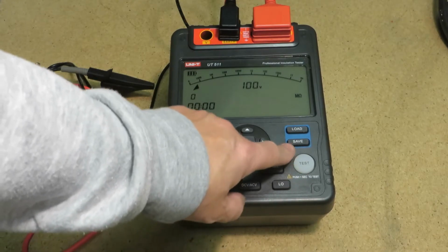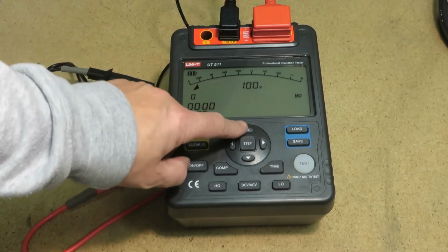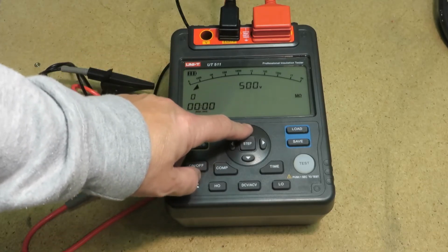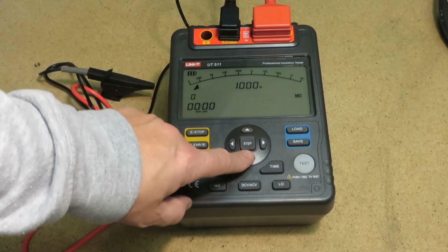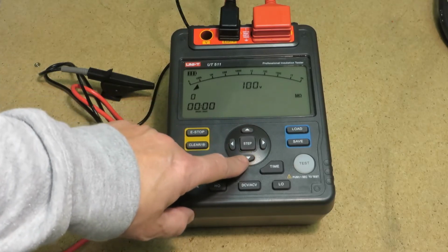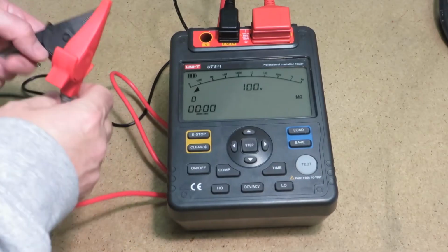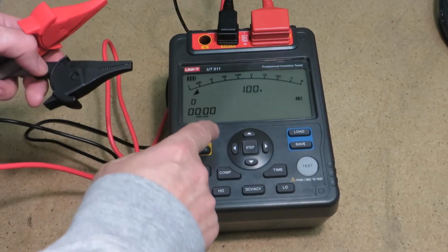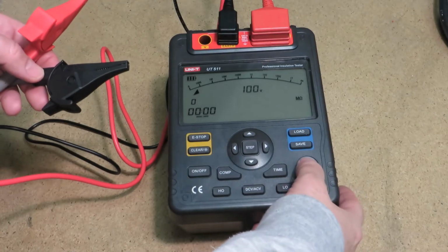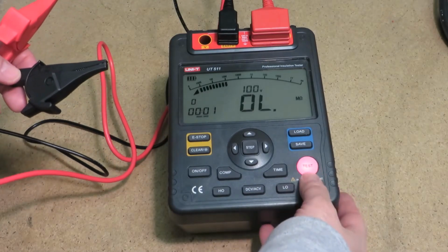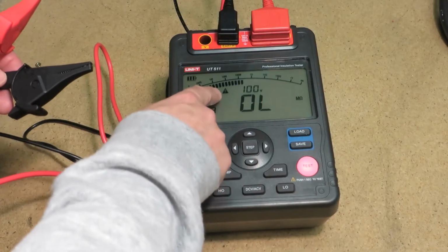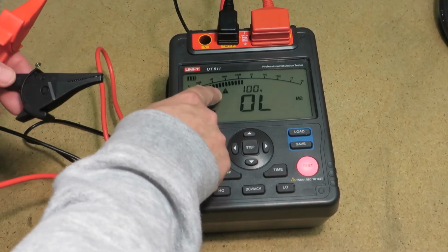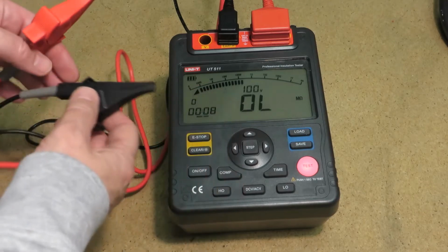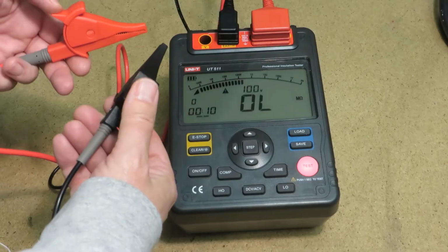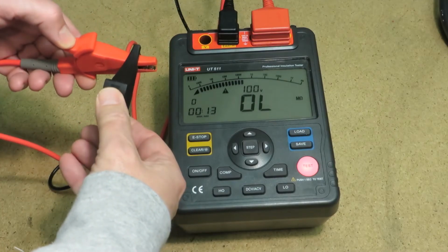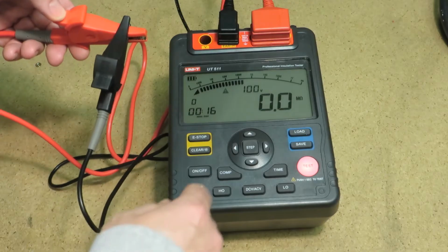You can save and load measured values. With the up and down arrows you can choose the measuring voltage from 100, 250, 500 and 1000 volts. I choose 100 volts for shorting the test leads, and long pressing the test button will provide 100 volt to the crocodile clamps. The bar graph will rise to a bit more than 100 meg ohm. A little flash sign will indicate that the measurement is in progress and that high voltage is provided to the crocodiles, so take care not to touch the leads. By shorting the leads, the meter will show 0 ohms.